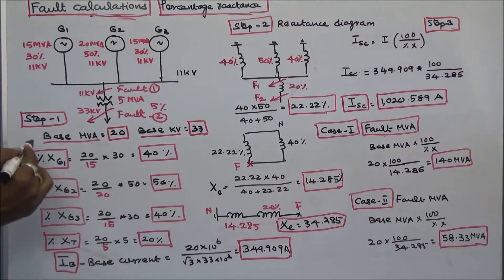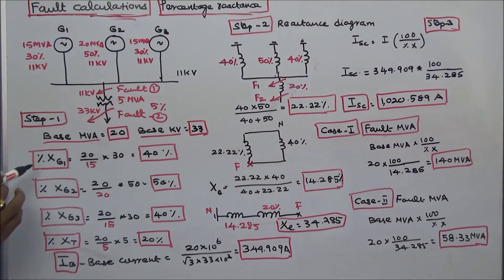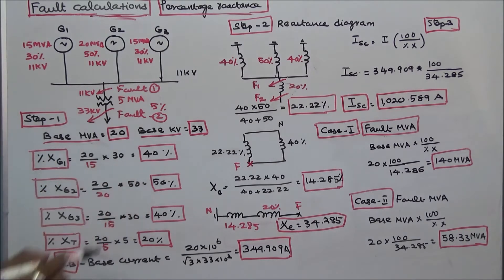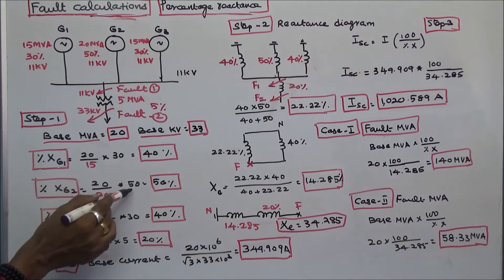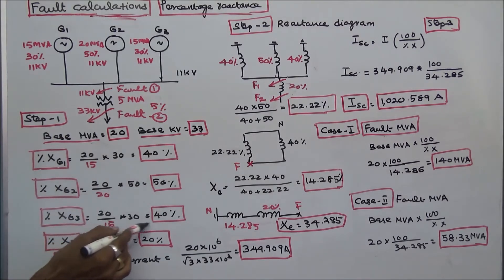Next, we calculate the percentage reactance of the generators and the transformer. %XG1 is equal to (20/15) × 30, which equals 40%. %XG2 is equal to (20/20) × 50, which equals 50%. %XG3 is equal to (20/15) × 30, which equals 40%.